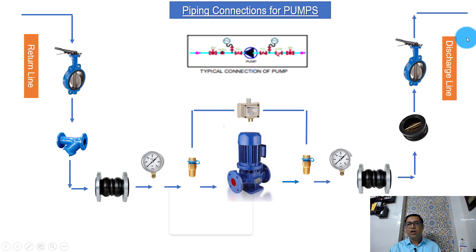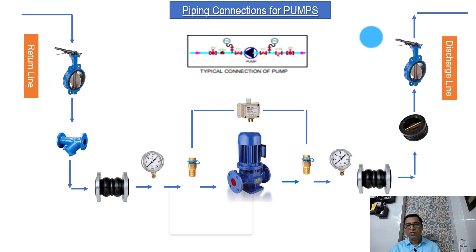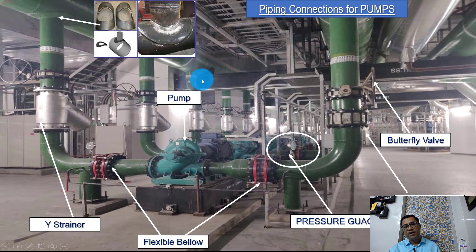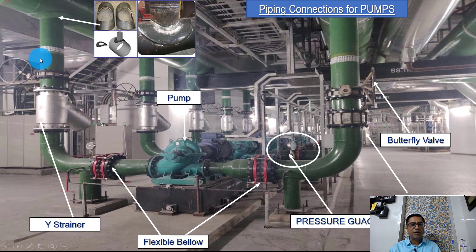So you can see here two butterfly valves. The first is at the starting point — these are the isolating valves. The same system is also denoted in schematic form. So this is the pump connection, my friends, and when you go to reality, this is how it looks. We have a butterfly valve over here. You can see a gear — this is a larger diameter butterfly valve and that is why this is a gear-operated butterfly valve.